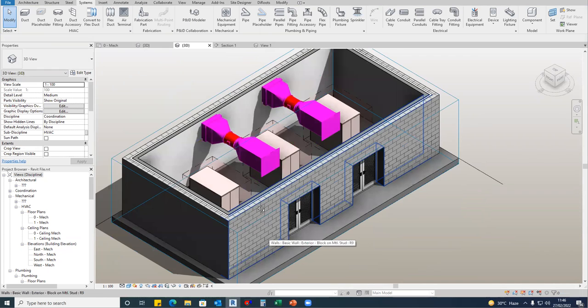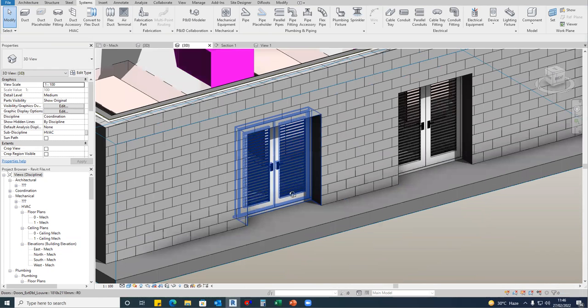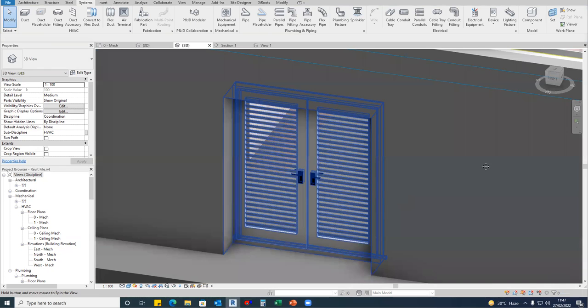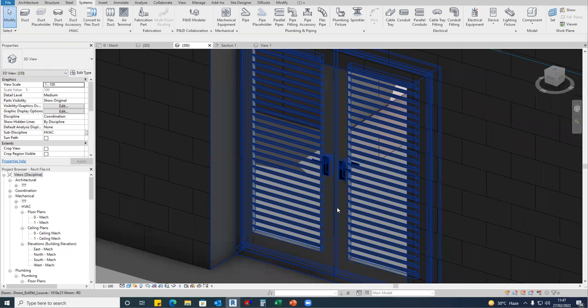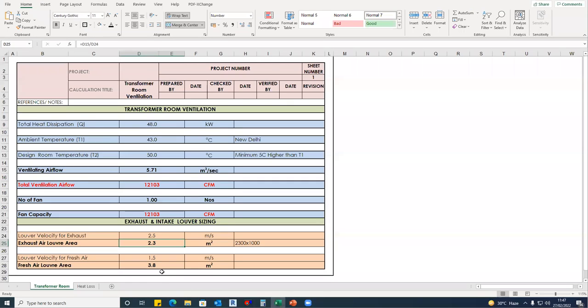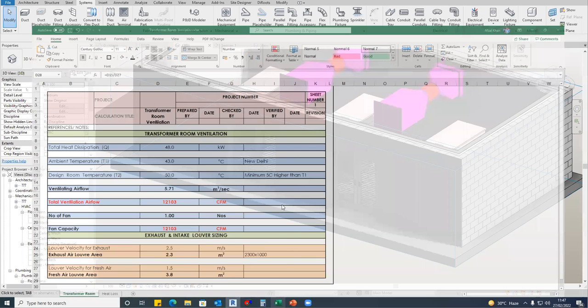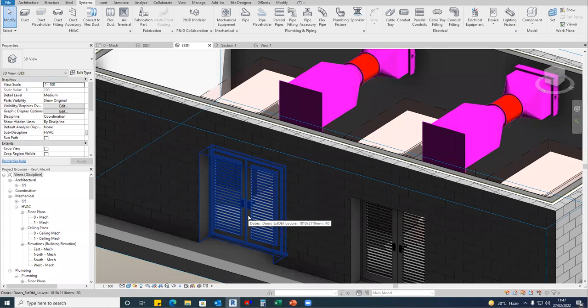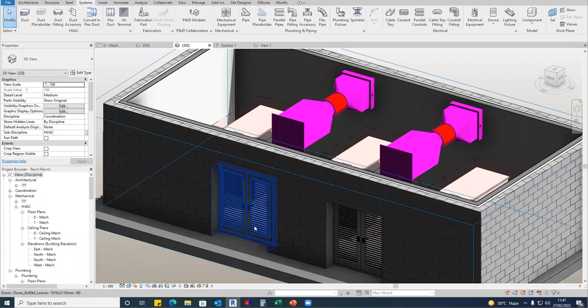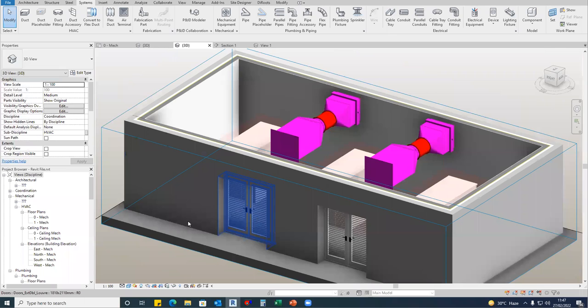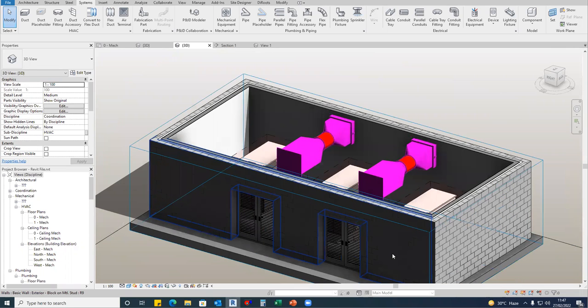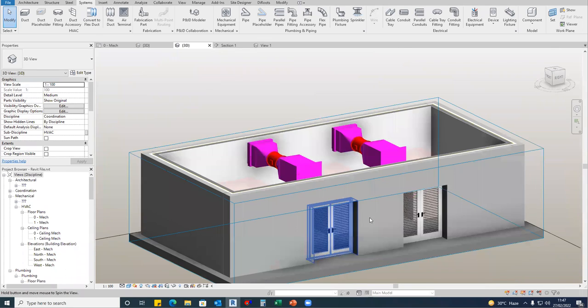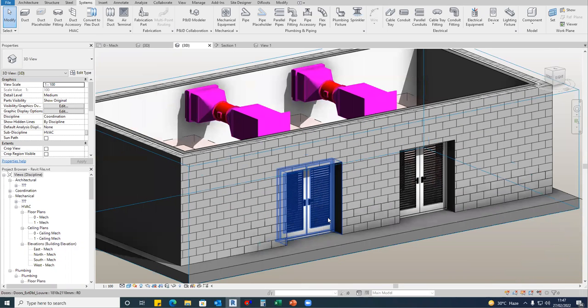So fresh air, sometimes what happens, the architect used to give louver doors. So in this case, if you see, these doors are louver doors. So whatever our requirement, for example, in this case, our requirement is 3.8 meter square of fresh air louver, right? So we can tell the architect that you must provide the free area, the area which is required for the fresh air, which is 3.8. So they'll take the size in the door itself. So in that case, you don't need to provide any louver over here. Okay, but if it is not a louver door, in that case, you have to provide the fresh air louver.